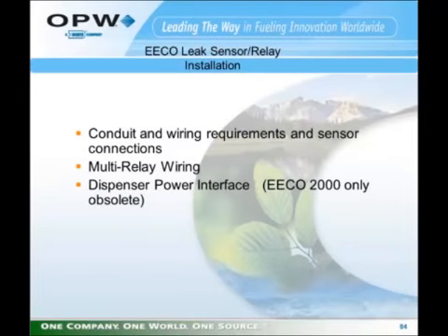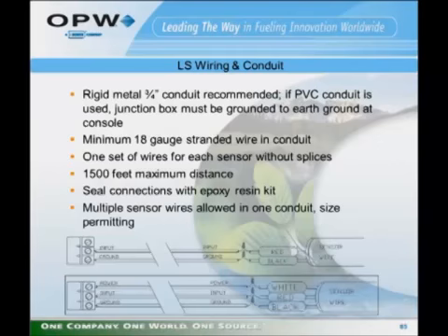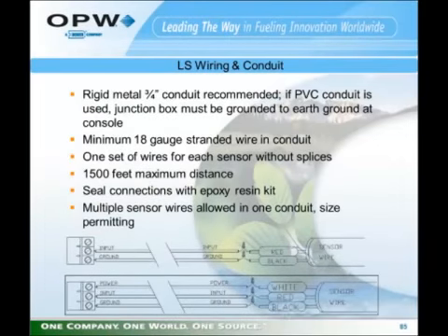Next, we're going to take a look at the conduit and wiring requirements for the sensor connections and the multi-relay wiring. This also shows dispenser power interface wiring, but because that has been obsoleted, we are not going to cover it in this presentation. The leak sensor wiring, like the probe wiring, requires rigid metal conduit, and that's what's recommended. If PVC conduit is used, like the probe, we require that a ground wire be inserted in that PVC conduit and must be grounded from the junction box to earth ground at the console.